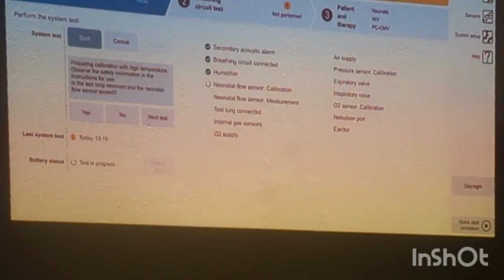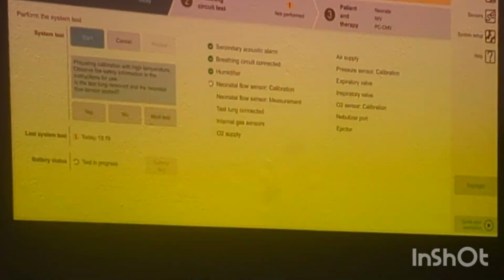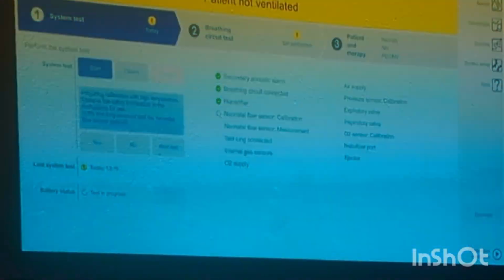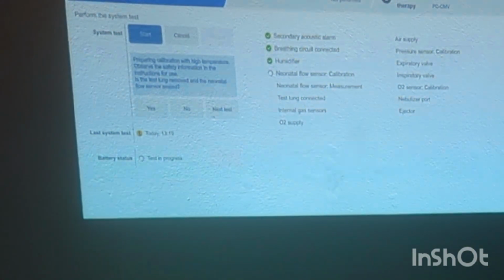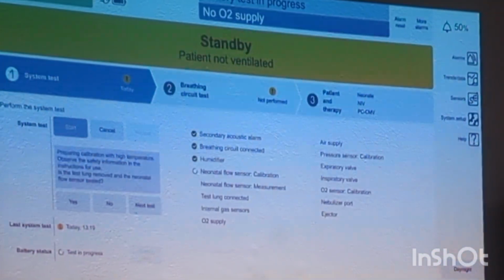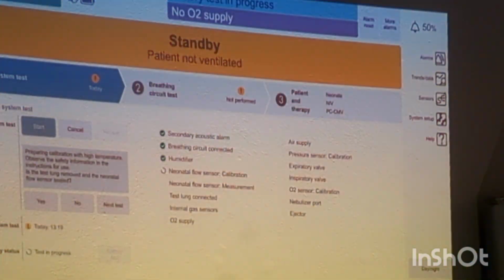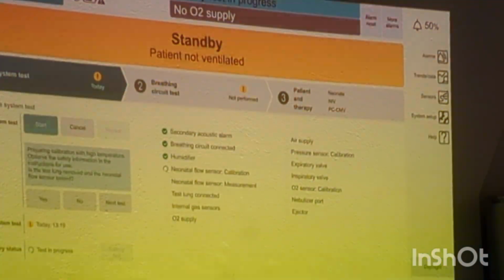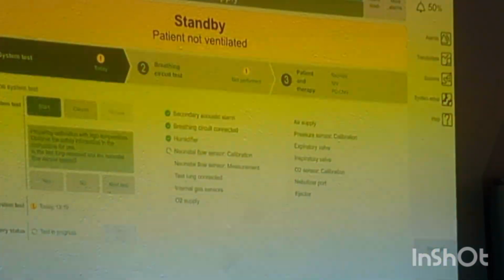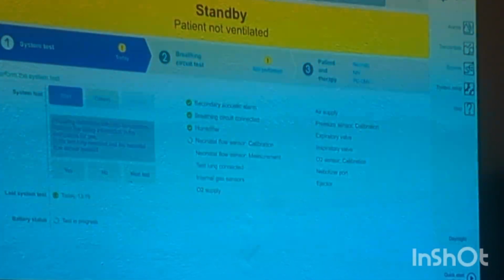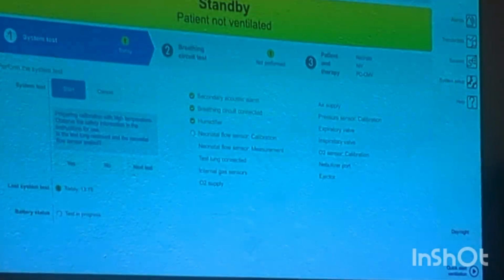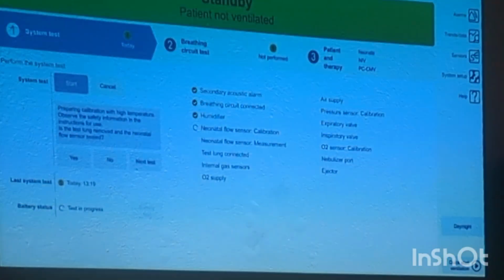Sometimes some tests like O2 sensor calibration and pressure sensor calibration don't require calibration every time, because pressure sensor calibration takes 3 minutes. That's why they have given the next option, so you can skip that test. But once the 3 months are reached, you have to do it. If you skip it at that time, it will come as red color. But if it was calibrated like 1 month before, if you skip it will not come as red color. So like here, calibrate everything.